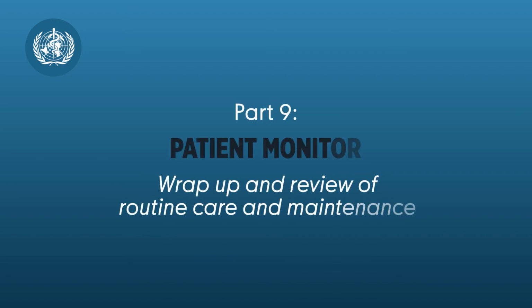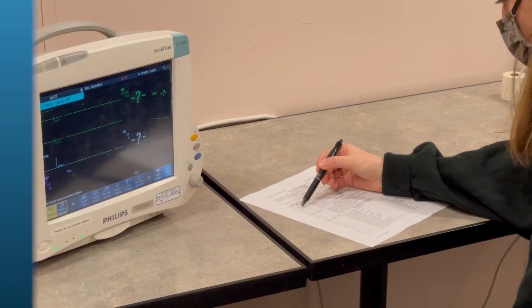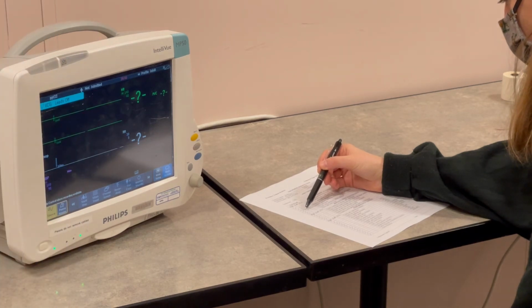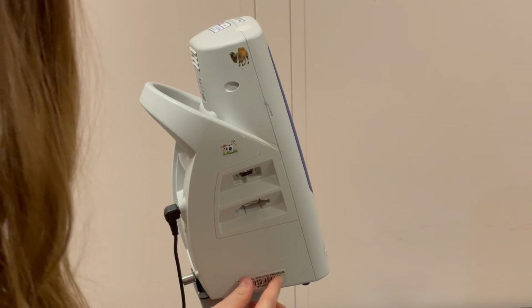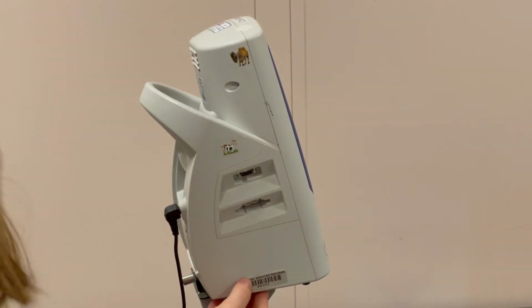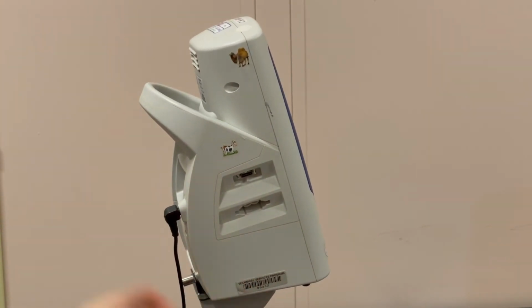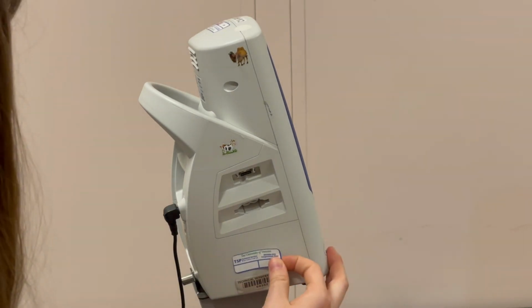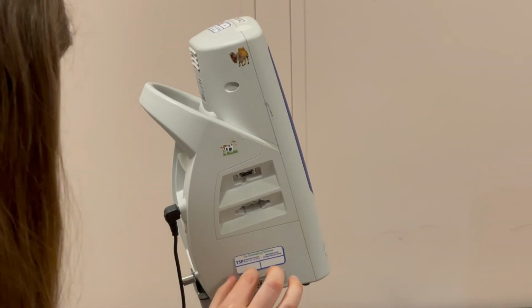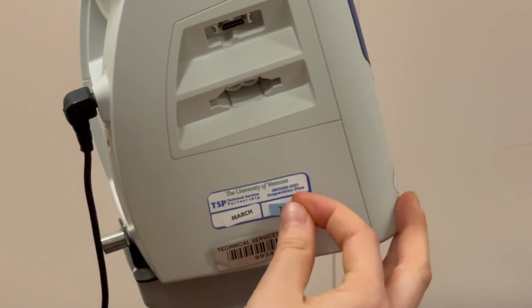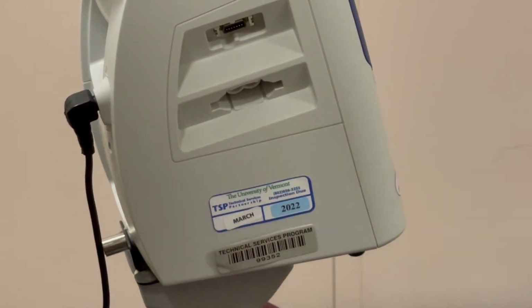You've now completed acceptance testing on your new patient monitor. If the device did not pass the acceptance test, double-check the failed section of the test. If verified, the vendor should be contacted directly or through your administrative process. If the device passes, apply the unique device identifier label or asset tag to the device. If other labels are required, such as battery replacement date or warranty end date, apply these labels as well.